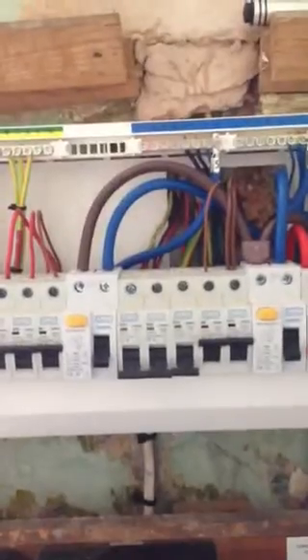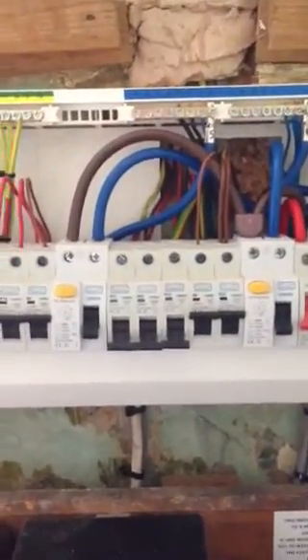Don't worry, boys and girls, the cutout fuse is good for prospective short circuits of up to 33 kA. So we've got plenty of safety built into the cartridge fuse, which is a BS 1361 type 2B, and it's indicated as 100 amp. And that's that really. We're safe to switch on at this point, and then we'll move on to Zs values and RCD testing.